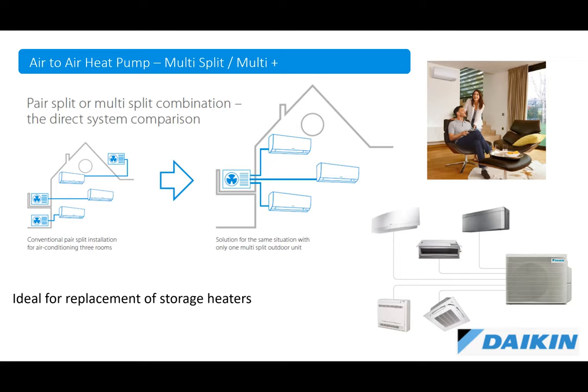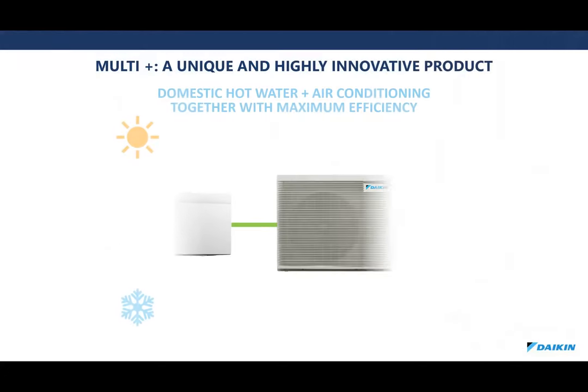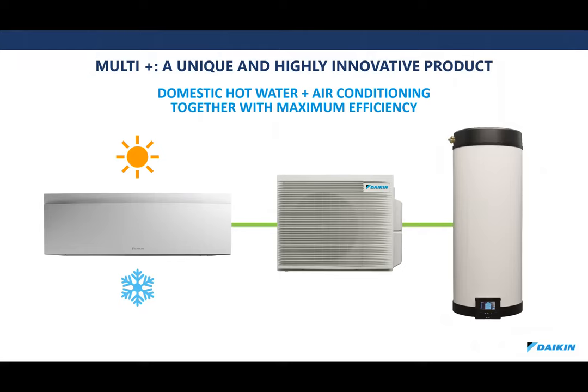So you can have up to five indoor units with one outdoor unit. Or when you look at the next slide here, we can actually combine a hot water cylinder with these indoor units. So when you combine the hot water cylinder, you can only have three indoor heating and cooling units. But when you put this whole system together, you now have a highly efficient heating, cooling and domestic hot water system that's very easy to install into an existing building where there has never been a wet system.